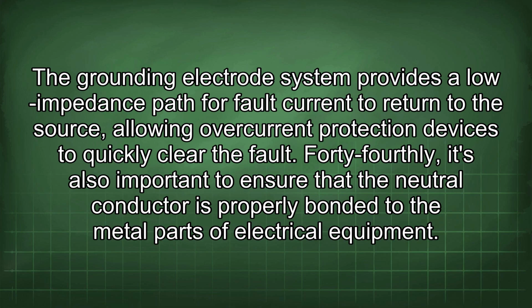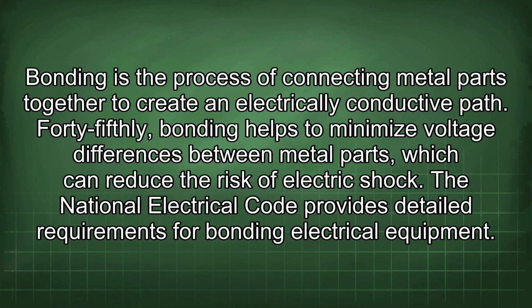44thly, it's also important to ensure that the neutral conductor is properly bonded to the metal parts of electrical equipment. Bonding is the process of connecting metal parts together to create an electrically conductive path. 45thly, bonding helps to minimize voltage differences between metal parts, which can reduce the risk of electric shock. The National Electrical Code provides detailed requirements for bonding electrical equipment.